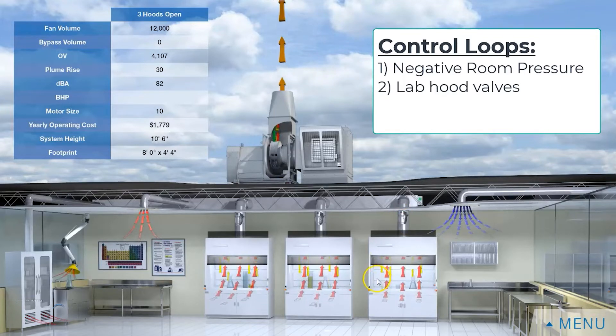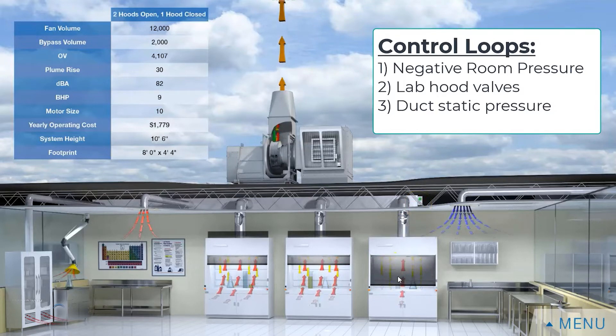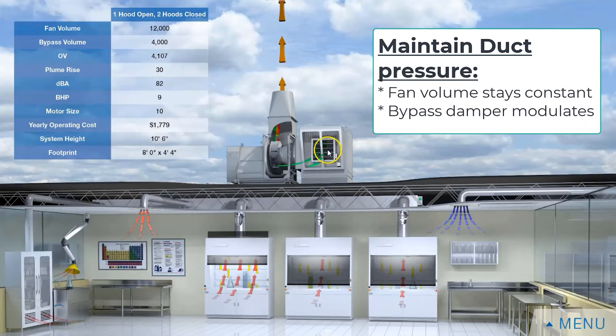The final control has to do with overall pressurization. Notice this little green light which is monitoring duct pressure. When my sash closes, I have a pre-engineered exhaust fan trying to pull air in from that system, but as that valve closes there's less available air. So when I close a sash I go to red for a few seconds — that means there's too much negative pressure in the duct system. So what we introduce is a bypass damper to bring in outside air to make up for what's not coming in through our chemical fume hood sashes.